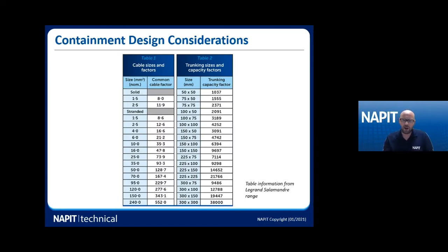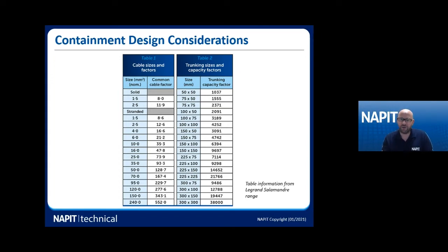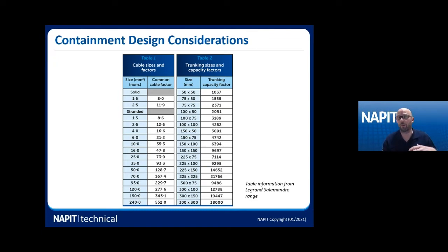These tables, kindly supplied by Legrand, show on the left hand side the cable sizes and their factors, and on the right hand side the trunking capacity factors. You add all your cable factors together and work out which size of trunking you need. As Richard said, you've got to do your design first — if your grouping calls for a bigger cable, it will have a different cable factor, resulting in a different trunking size.